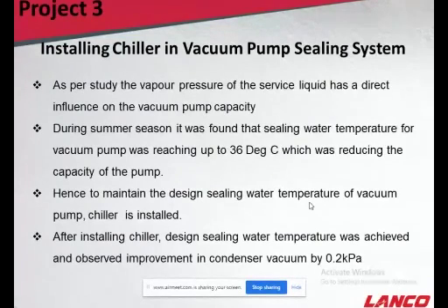And this impact was seen as a vacuum improvement of 0.2 kPa. If you see the chiller panel, the inlet temperature was 36 and it was maintaining 30 degrees, just below the design value of 32, to compensate for this. So when we were giving the design sealing water temperature, we were able to get the design capacity of the vacuum pump and an overall improvement in the vacuum for the period when these temperatures are higher than the design. These days, in the peak summer, all plants have this vacuum problem. But to improve this vacuum, if we work on the vacuum pump sealing water temperature, this effect we can realize.